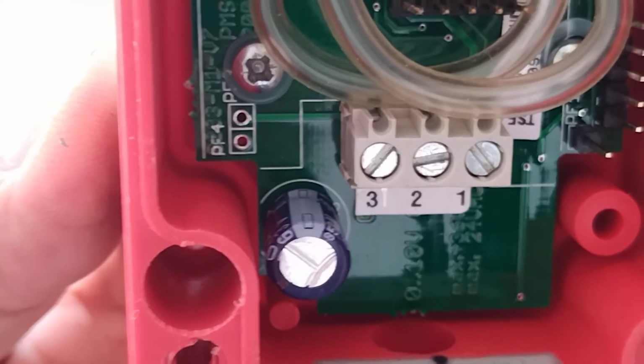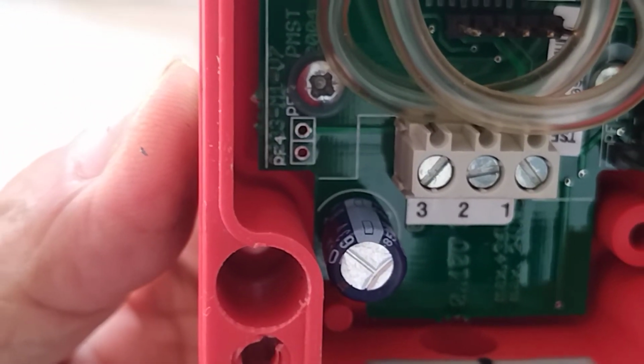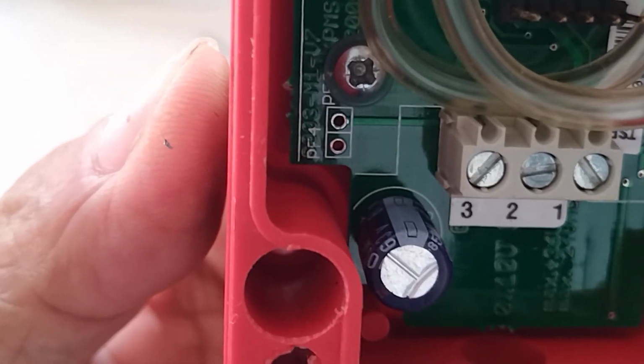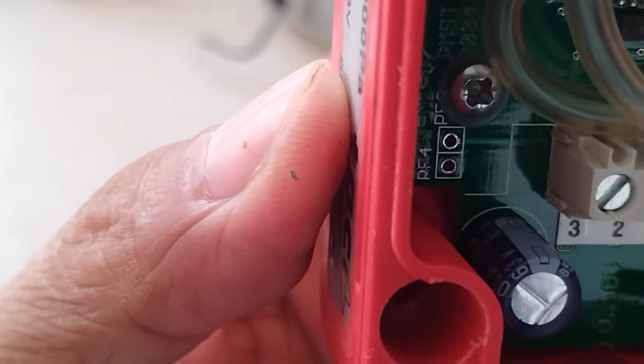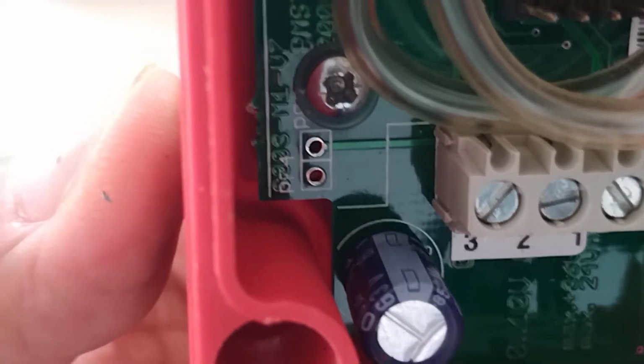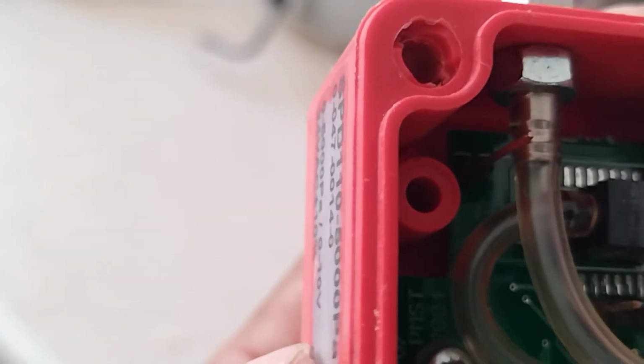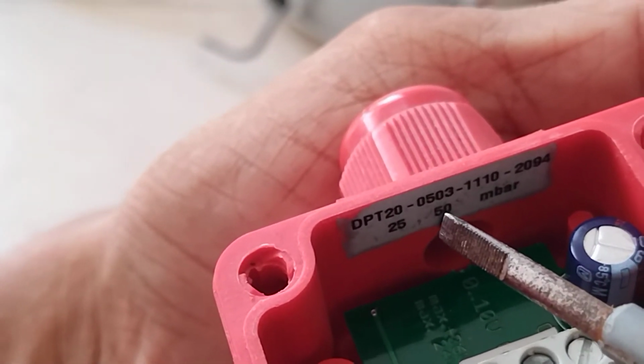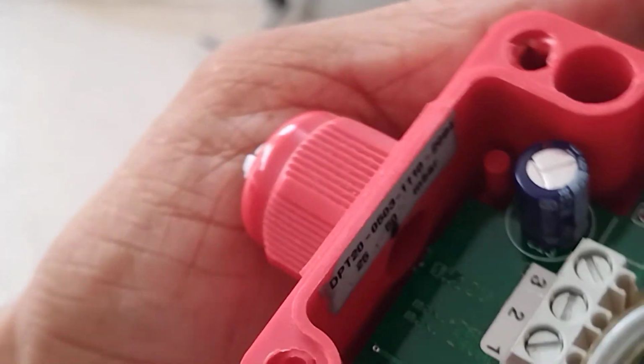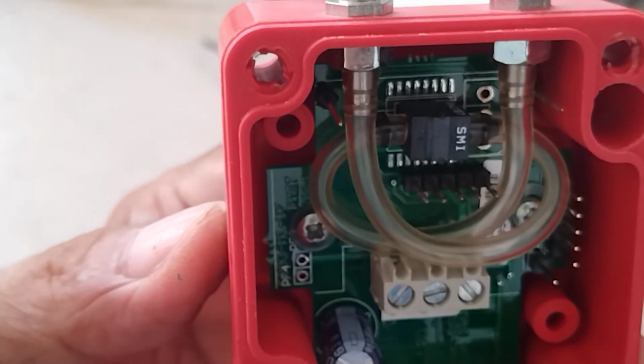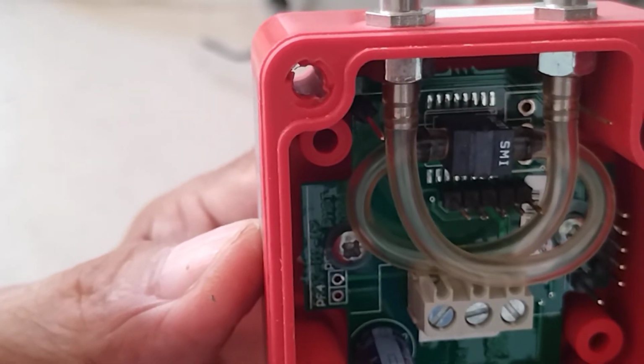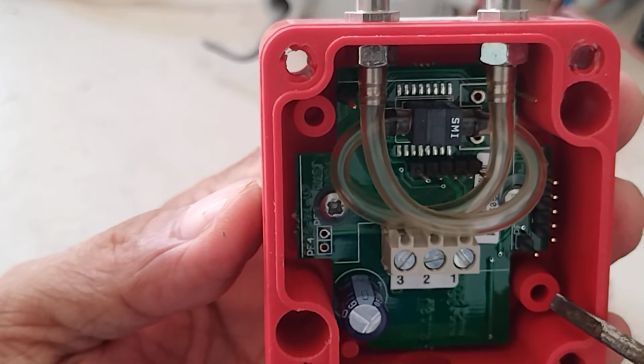So meaning, if it will give you 0 volts output signal, meaning it is not sensing any differential pressure across the fan. So 0 meaning maybe the fan is off. But if it will give you 10 volts DC, actually this is DC, if this one is giving you 10 volts DC, then meaning it's sensing the maximum range, which is 50 millibar or 5000 Pascal. Okay? So that is the most important thing that you have to know when you are going to use a differential pressure transmitter.